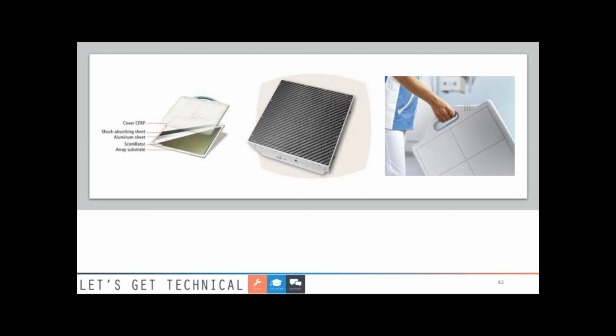Now, with film, basically you're going to want to use a step wedge in quality control, because the problem is the film gets old and wears out if it just sits there. The cassettes are good, but you're generally not going to calibrate them. It's all the rest. Either it's good or it's bad, which is nice for you, because then you can prove it with other film or another cassette, and you're out the door. It's only with cassettes.